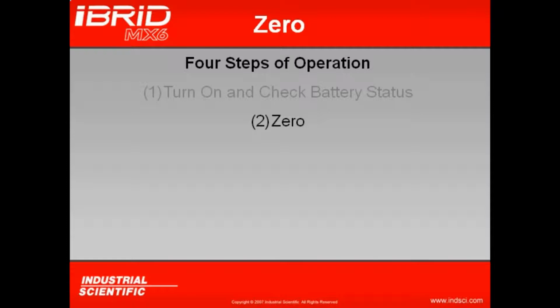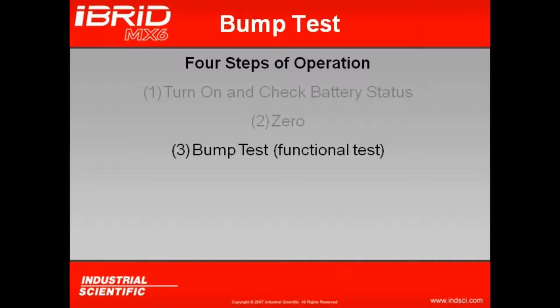For example, let's say we zeroed the instrument, but in the environment was 5 ppm of carbon monoxide. When I go outside to a true clean air environment, my CO sensor will now read a -5 because the 5 ppm I told it was 0 will have disappeared and the instrument will have no choice but to then go negative. So we always zero in clean air.